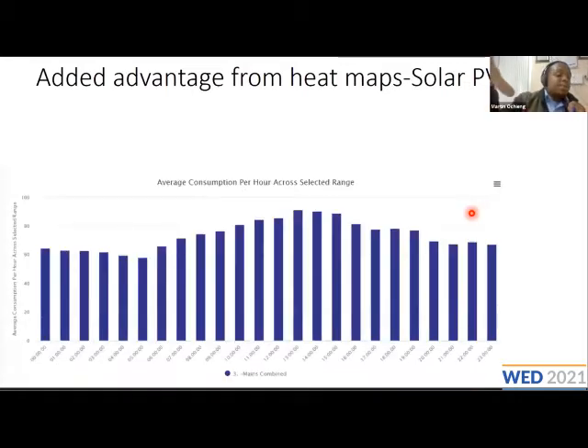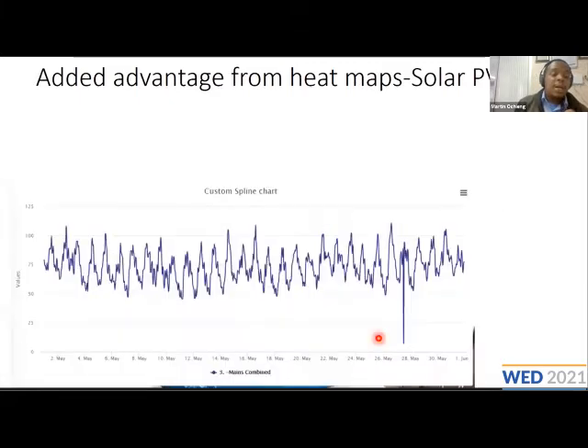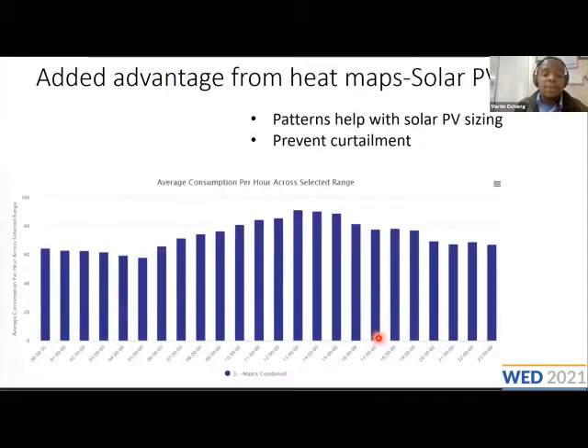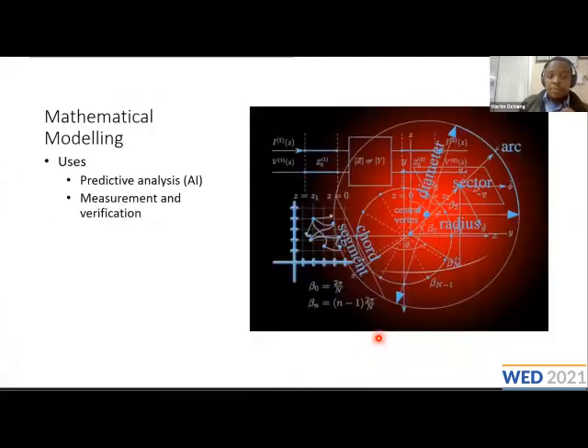However, drawing from the heat maps themselves, how they segment energy consumption, you can come up with a chart like this that looks at average energy consumption across a specific range per hour. It can help us identify exactly what the trend is in average energy consumption over specific hours of the day. And in case you are looking to set up a grid solar PV system, this information from around 8 a.m. to around 5 p.m. would be very, very useful in helping us identify how to size solar PV compared to this chart over here, which will give us that level of detailed information. So it can help us identify patterns and prevent curtailment whenever we size solar PV.